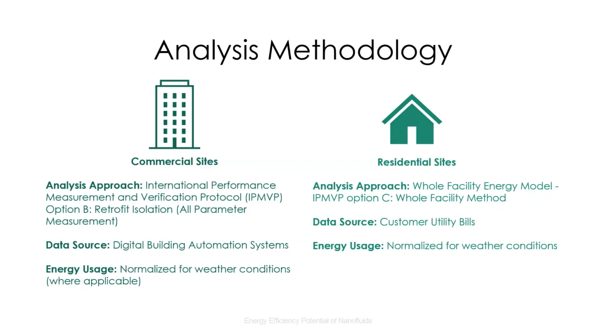So these efficiencies are in the form of kW per ton for chiller systems and therms of natural gas per MMBTU for boiler systems. Specifically for the commercial systems, we looked at it on a system basis, so that energy input into that system was compared to the HVAC system's heat transfer to determine the operating efficiency we used. We downloaded data at regular intervals or obtained automation data from the facility owners as it was available. We did add metering points to existing automation systems where necessary. And since standard heat transfer equations don't apply to this technology, according to the manufacturer, we developed alternative analysis approaches.